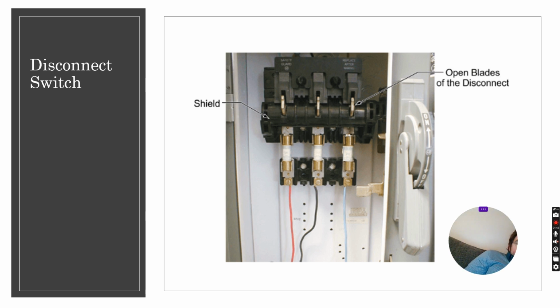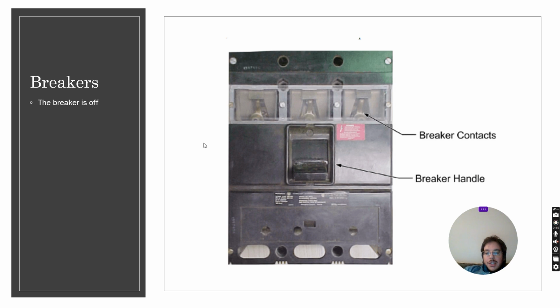But basically, if we go back to our breaker, we're going to learn more about this, but our breaker is designed to disconnect the power. Power comes in from the panel. This is normally mounted so that this bottom part faces the center of the panel, and this part faces the outside. Power is coming into the breaker from the panel, and then it's coming out of these contacts, which have wires typically, and these go to our equipment. If too much current flows through the breaker, it trips and breaks the contact between the 2 sides, and then we don't have power anymore.